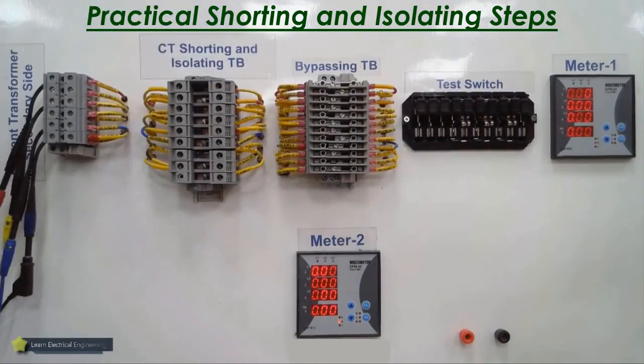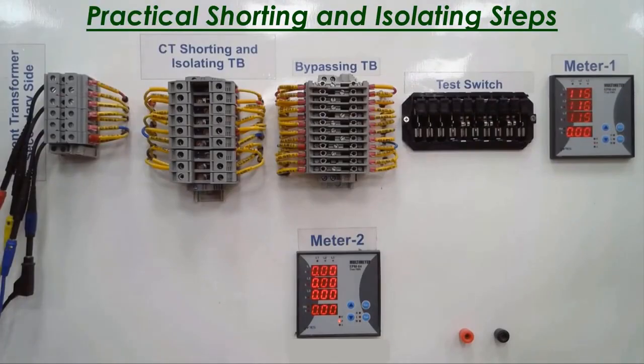I will start injecting my currents. Here, I have set the ratio on the power meters to be 600 to 1. As we can see, the currents are balanced on the 3 phases.